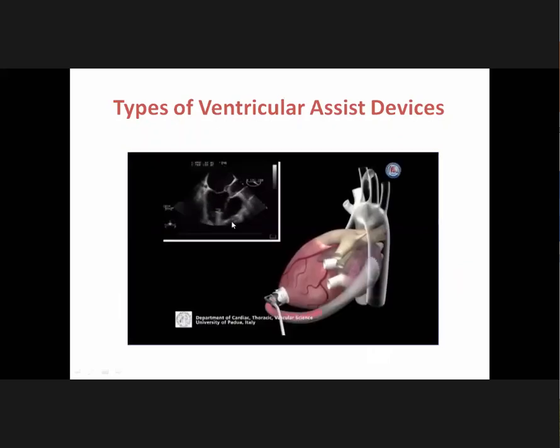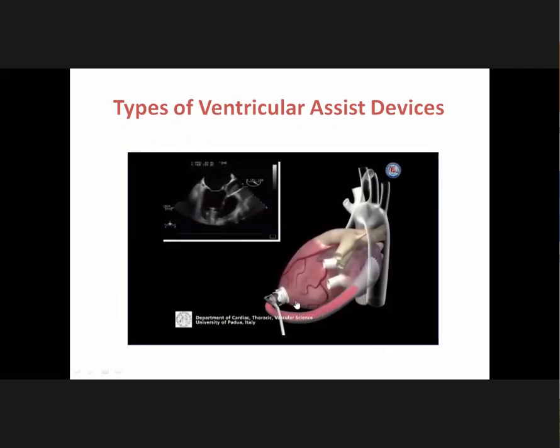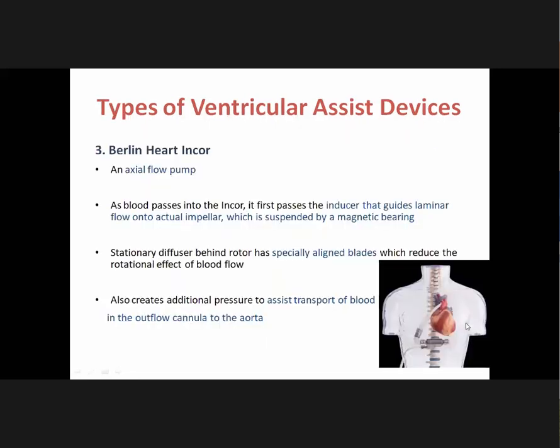The Jarvik 2000 is an axial flow continuous flow pump with an intraventricular position — the whole pump sits within the LV cavity. Its impeller is the only moving component located in the center of the titanium housing; flow is directed through the outlet graft by stator blades near the pump output and returns to either the ascending or descending aorta. It can pump around 8 liters per minute and the chance of infection is very rare. It weighs around 200 grams. The Berlin Heart INCOR is also an axial flow pump where blood passes through an inducer guiding laminar flow onto an impeller suspended by a magnetic bearing, which improves blood transmission through the outflow conduit.